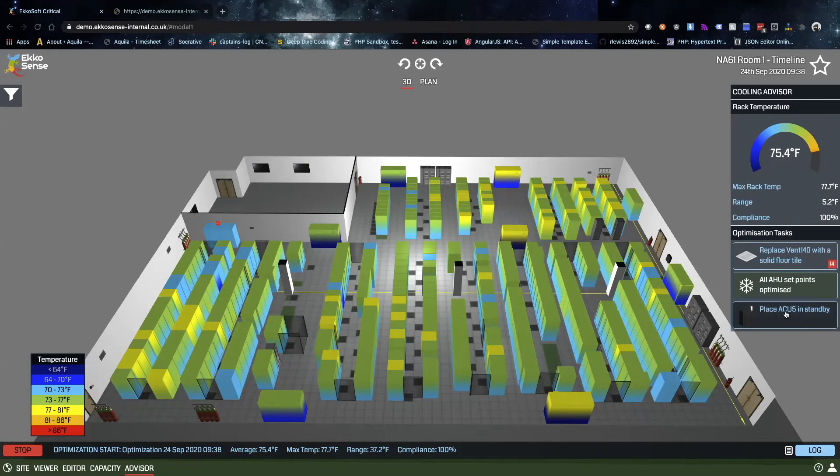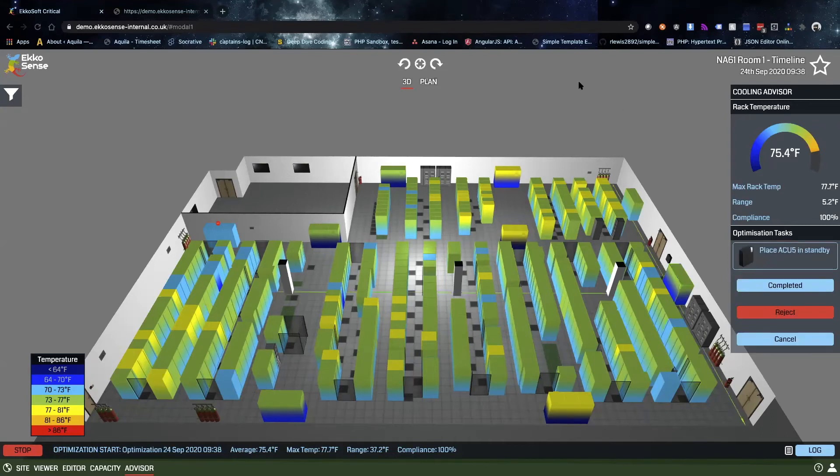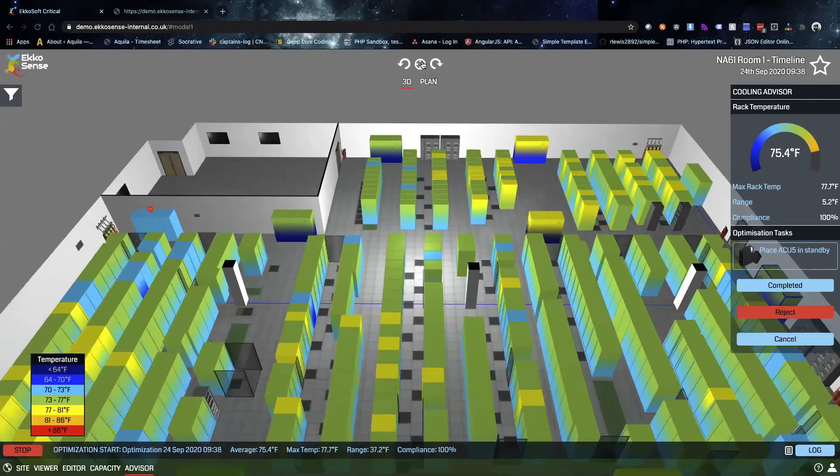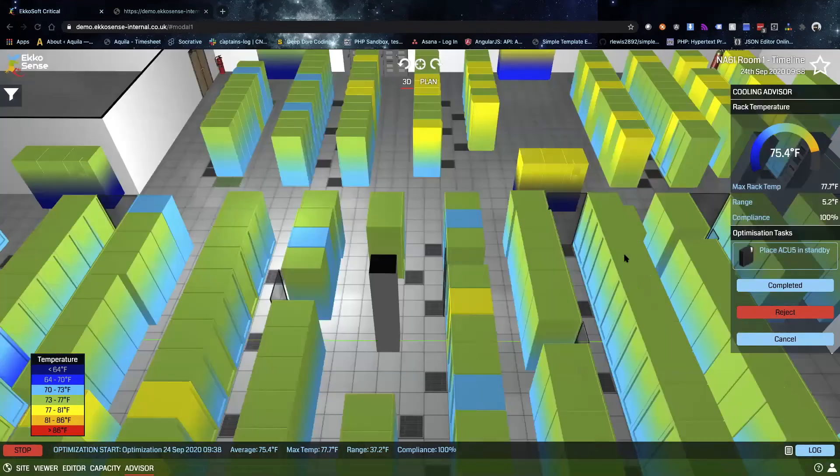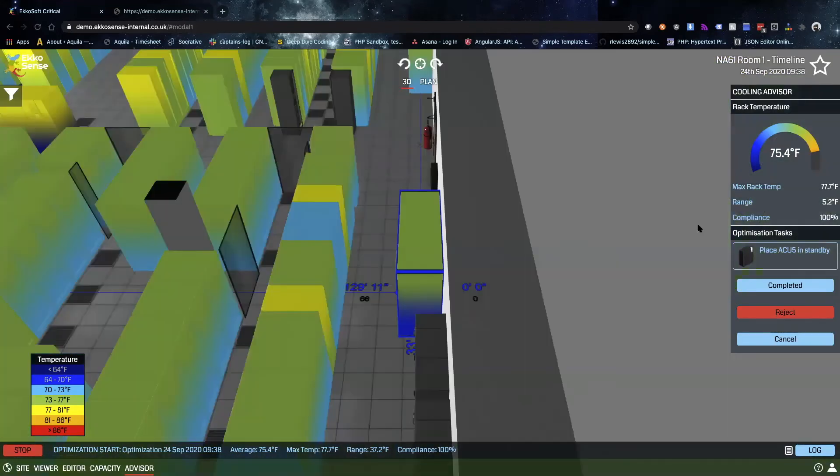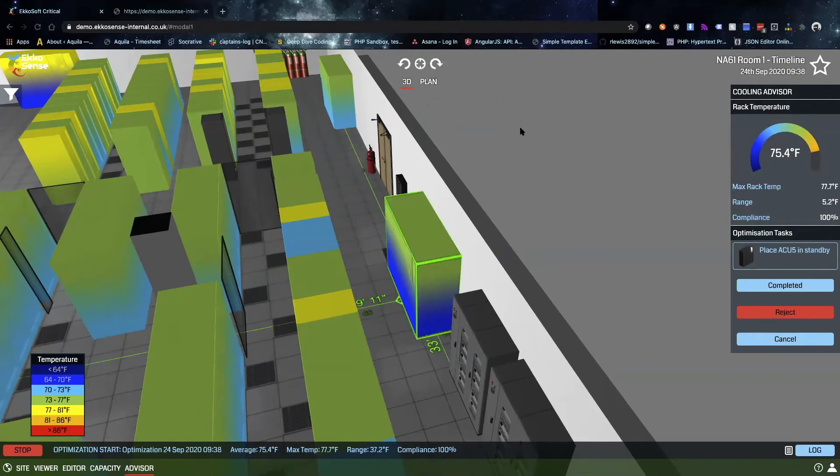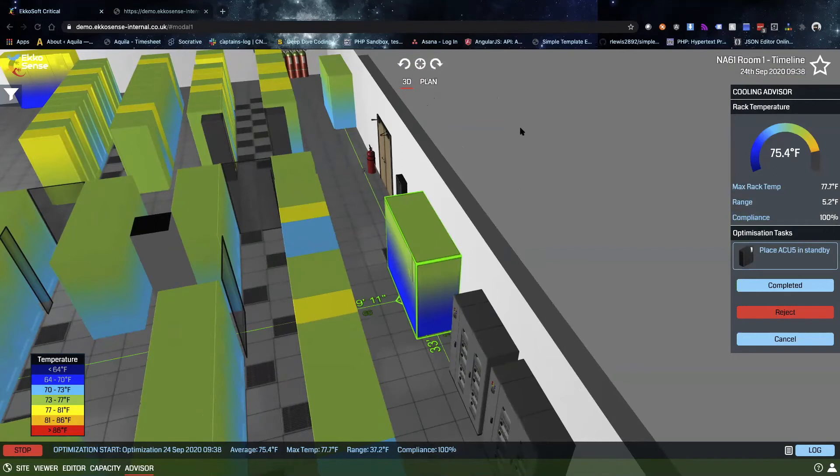The software is also looking at the cooling units and identifying which of them may be able to be turned off. We can see when we follow this recommendation and look into it, there's a recommendation to turn this cooling unit number five and place it in standby. Just by clicking on that target button, it zooms into where that recommendation is. Based on the software's analysis, it's seeing that this cooling unit is not picking up very much load.